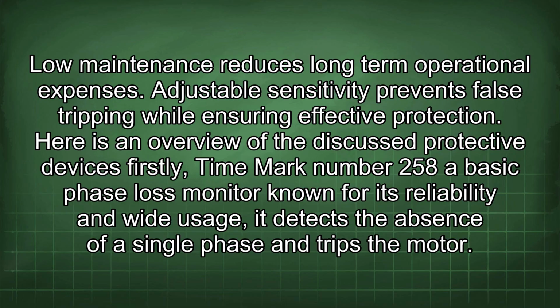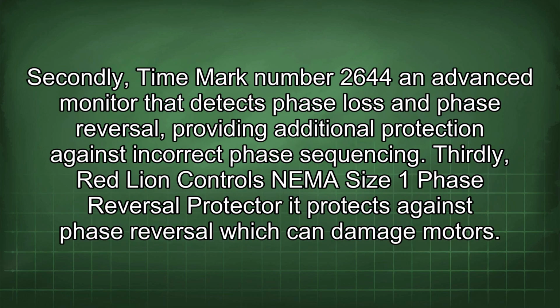Here is an overview of the discussed protective devices. Firstly, Timemark number 258, a basic phase loss monitor known for its reliability and wide usage. It detects the absence of a single phase and trips the motor. Secondly, Timemark number 2644, an advanced monitor that detects phase loss and phase reversal, providing additional protection against incorrect phase sequencing. Thirdly, Red Lion Controls NEMA Size 1 Phase Reversal Protector.